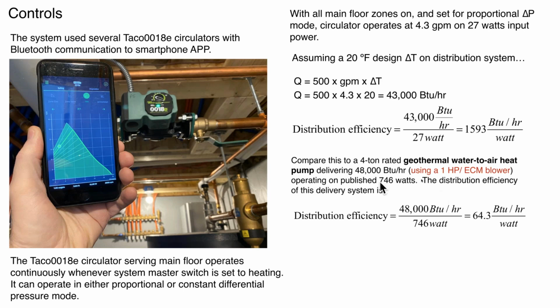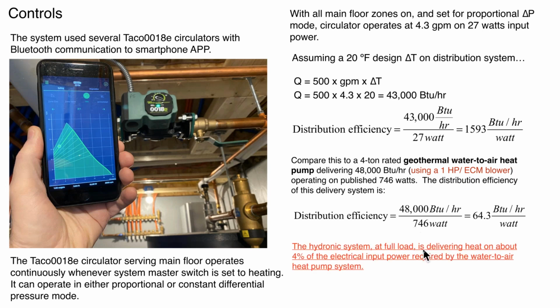So that was actually based on some specs I took off of a water to air heat pump unit with a 1 horsepower ECM blower in it. And just to again emphasize the advantage of dealing with a hydronic distribution system compared to a forced air system is much lower wattage for a given rate of heat delivery. And that fundamentally all goes back to what we talked about last week. That is the much higher heat capacity of water compared to air. Okay.